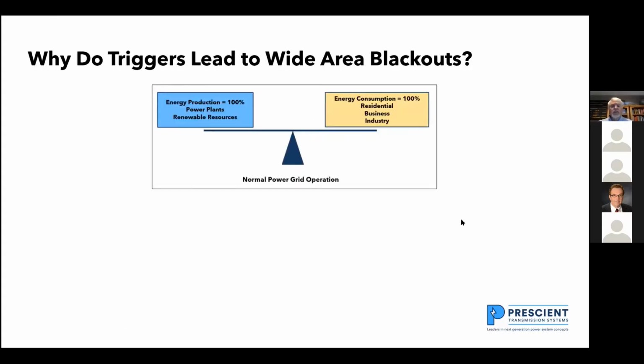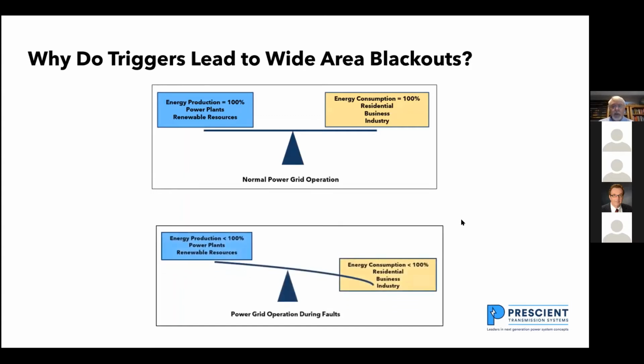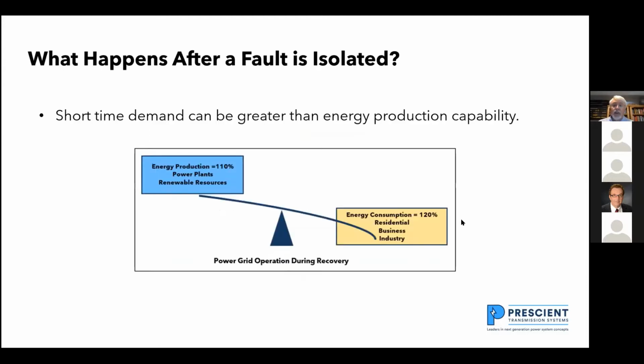The reason why we're concerned about triggers is that normally the energy production and the energy consumption are balanced. It's a steady state balance. When faults occur, the balance is disturbed and all the power we're producing is not transmitted. And since it's not all transmitted, it's not all received. That means that we're going to be storing more kinetic energy in machines during a fault, and we're going to have a shortfall of energy at the consumer end. The problem that we're really concerned with is after the fault is cleared.